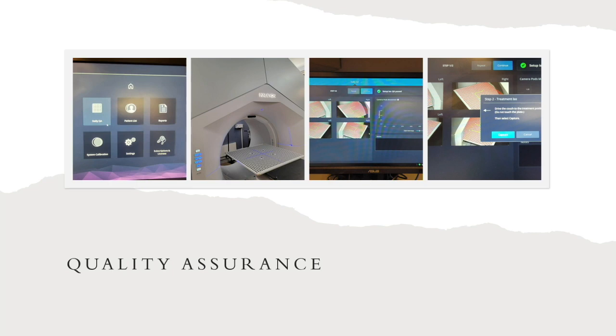Okay, moving on to my quality assurance slide. So at the computer monitor, we're going to be selecting the daily QA, which all in all takes maybe 3 minutes in the morning. In general, quality assurance for an Ethos or a Halcyon is extremely quick compared to our traditional linear accelerators. We allow a 30-minute time slot in the morning to do the quality assurance on the machine, and that also includes the quality assurance of our AlignRT system.